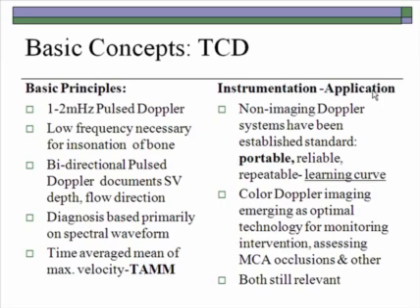Non-imaging Doppler systems have been the established standard since 1986. They're portable, reliable, and the exams are repeatable, but the learning curve is quite significant and there is no image to guide the placement of the sample volume. Color Doppler imaging is emerging as an optimal technology for monitoring intervention because you can visualize and assess MCA occlusions and other issues. Both are still relevant and still have very specific utilization.